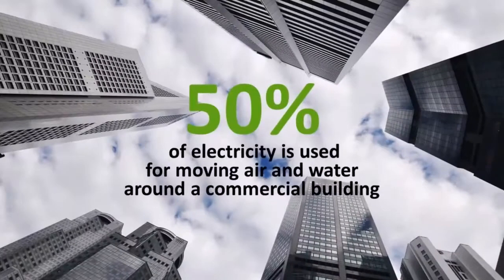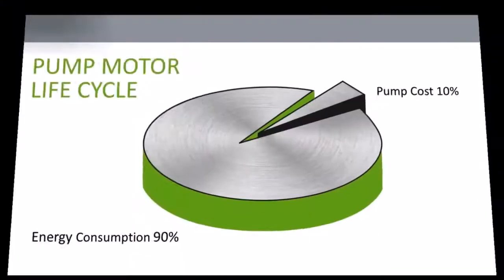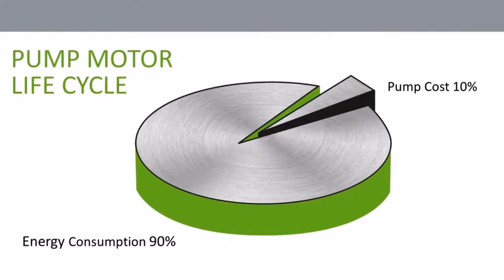We use a lot of energy in this country, and most of that energy is used to move air and water around a building. About half the electricity in commercial buildings is just used to move air and water around, so a VFD is a big way to save energy there. If you look at a typical pump motor, 90% of its life cycle cost is the energy it consumes, and only 10% is the actual cost of the pump motor. A VFD can cut that in half.